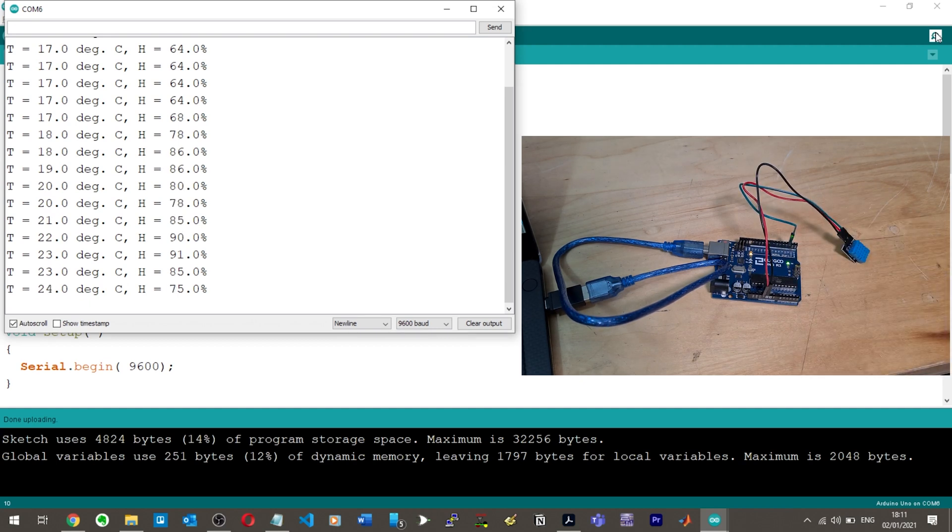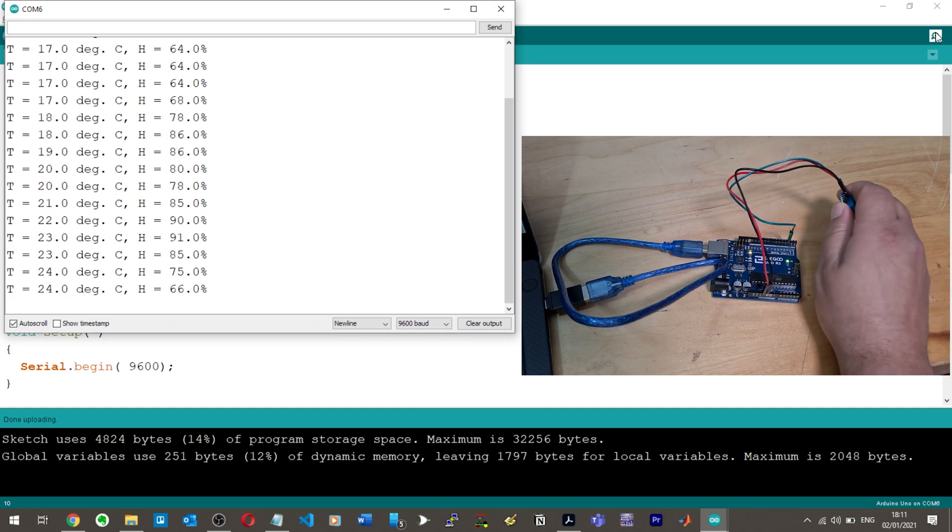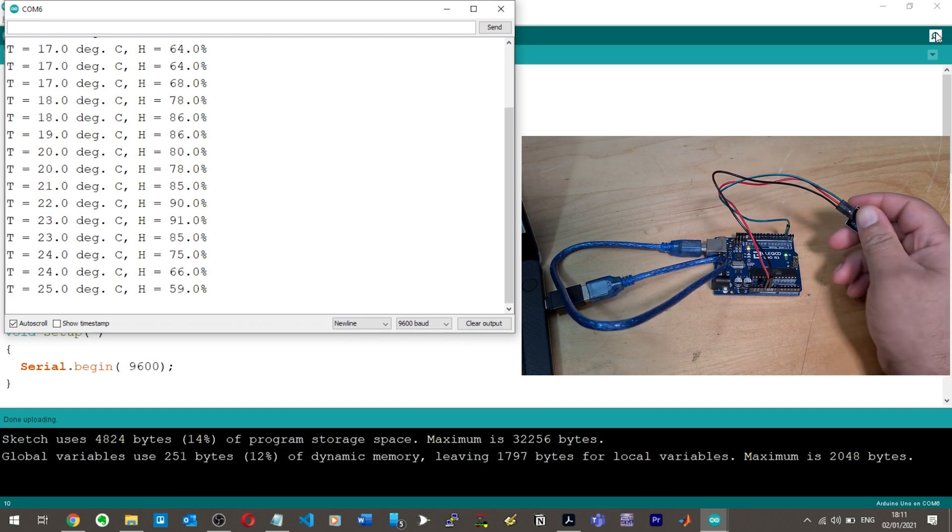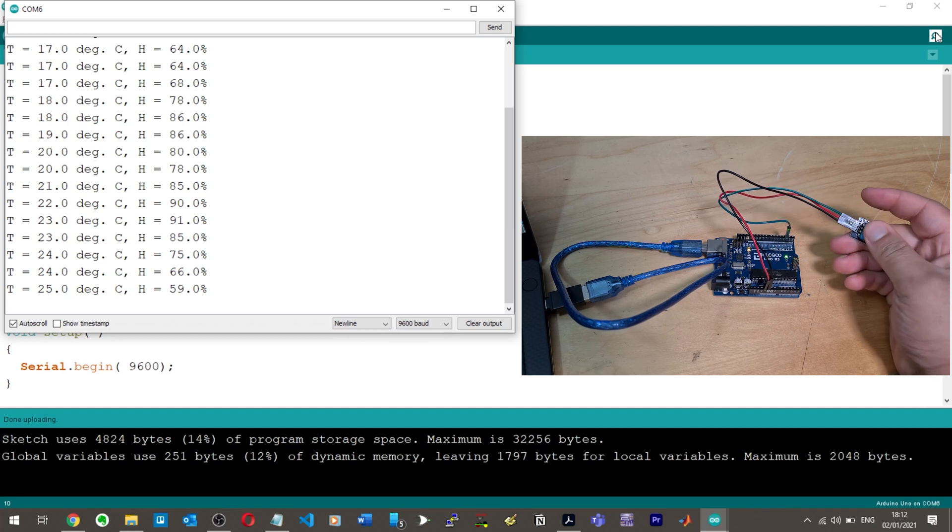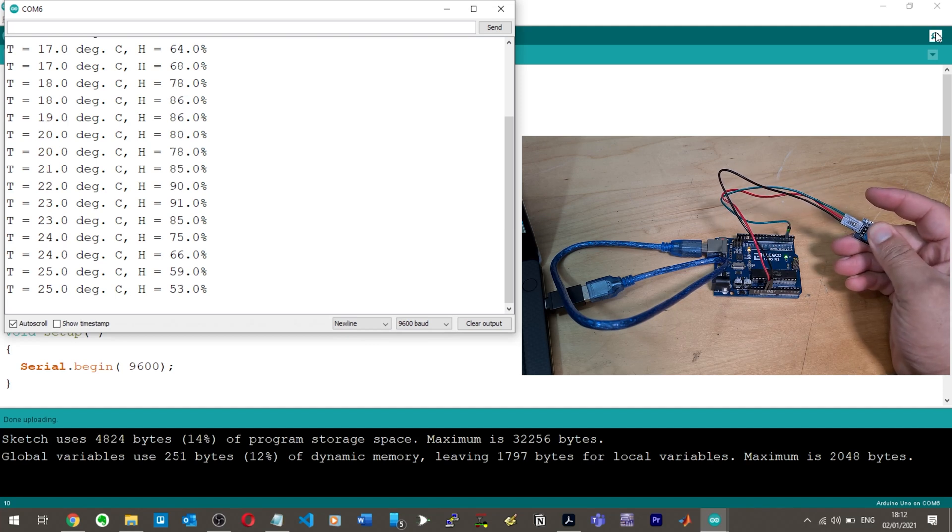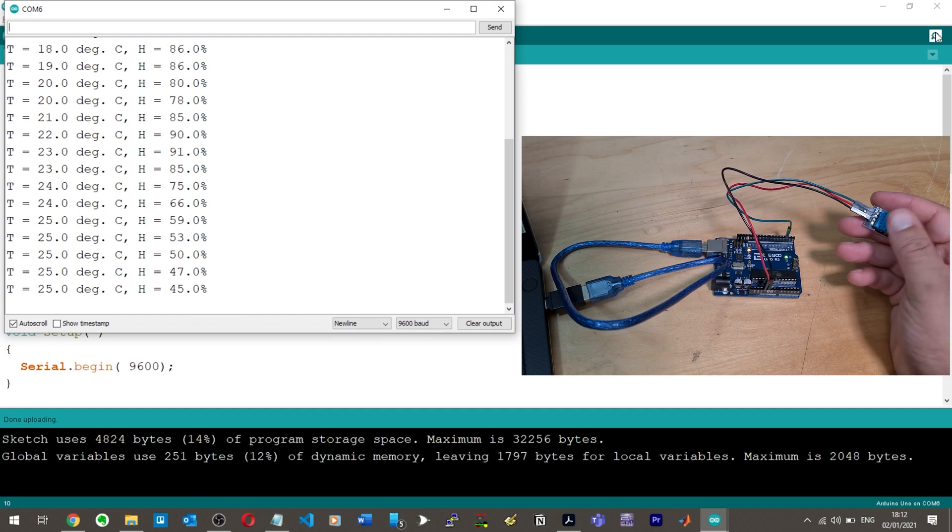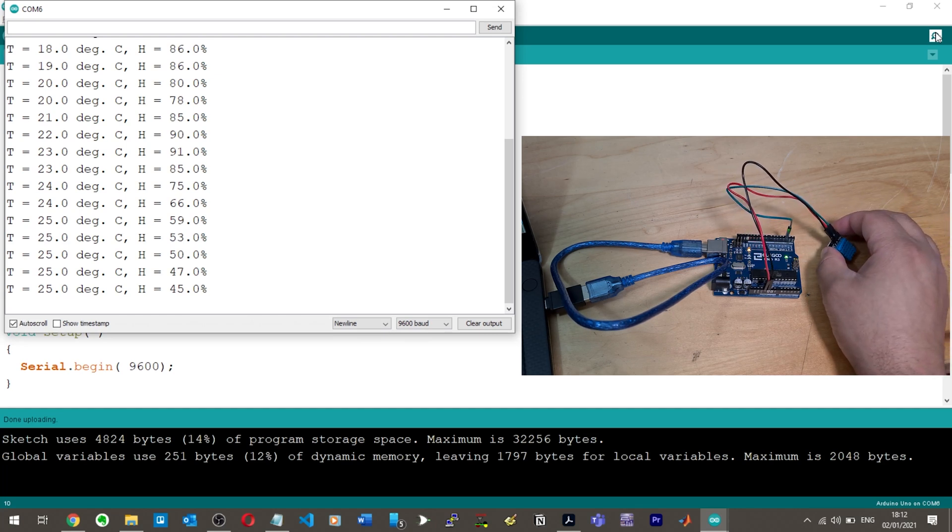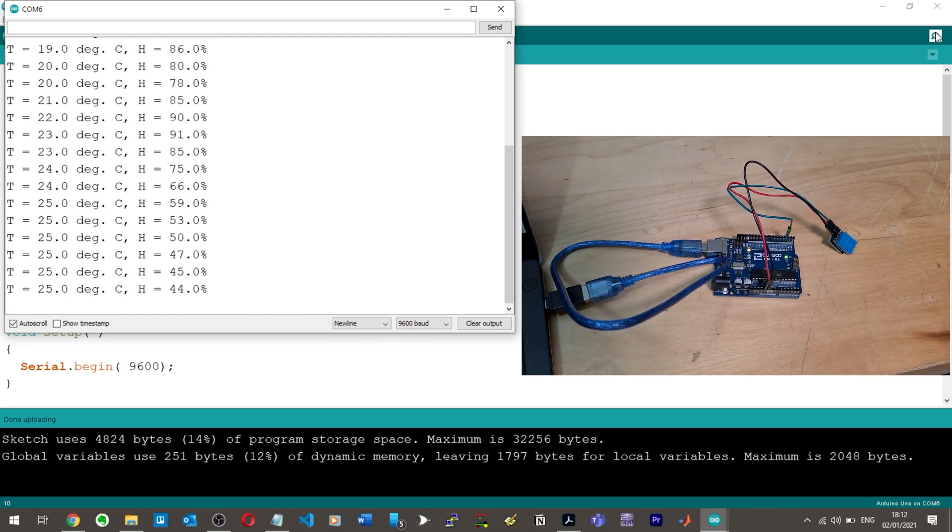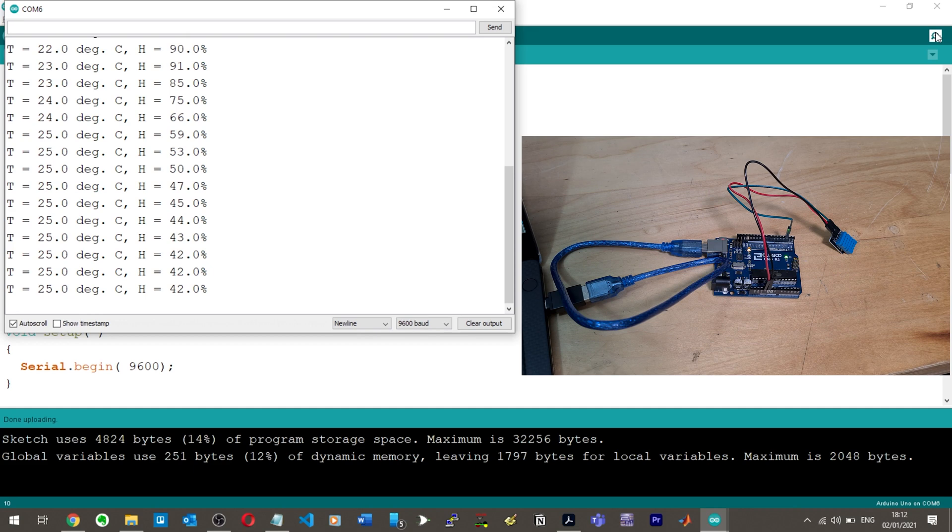Okay, so I've let go. I want to see if it drops down. Yeah, so humidity is dropping down. So it's actually very responsive. Temperature is still at 25 degrees though. The humidity has dropped even lower than it was. It was at 60% to begin with. How's that possible? I don't get that. It was at 60% originally. By me holding it. So it responded quick to the temperature increase, but for whatever reason the temperature isn't decreasing fast.